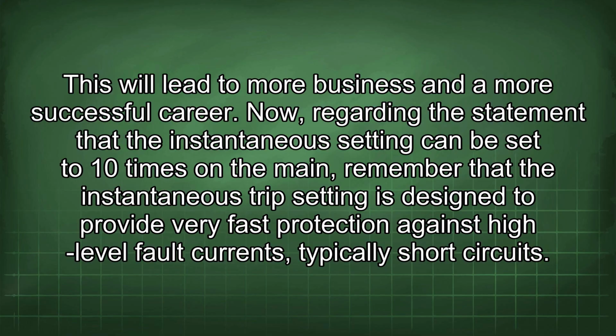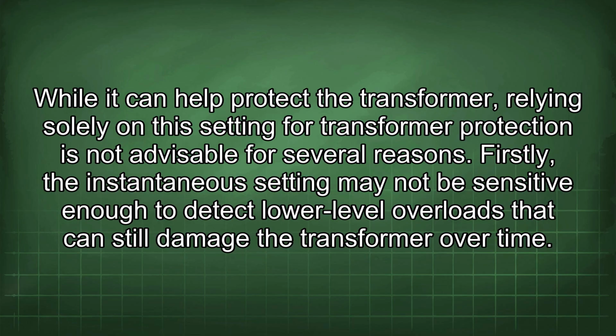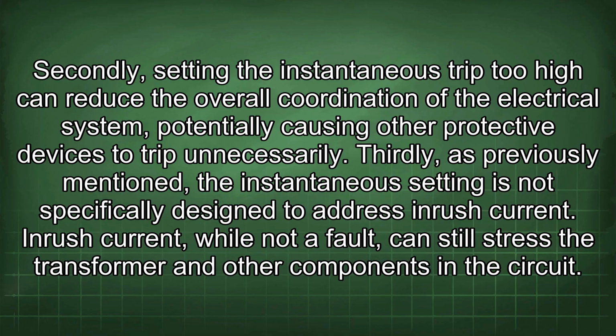Now, regarding the statement that the instantaneous setting can be set to 10 times on the main, remember that the instantaneous trip setting is designed to provide very fast protection against high-level fault currents, typically short circuits. While it can help protect the transformer, relying solely on this setting for transformer protection is not advisable for several reasons. Firstly, the instantaneous setting may not be sensitive enough to detect lower-level overloads that can still damage the transformer over time. Secondly, setting the instantaneous trip too high can reduce the overall coordination of the electrical system, potentially causing other protective devices to trip unnecessarily.